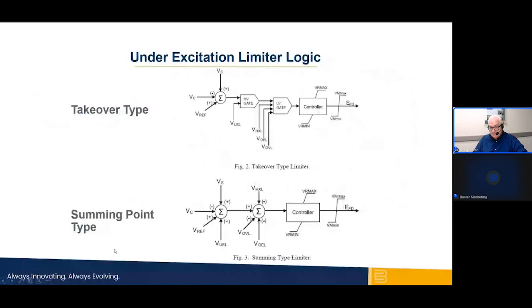Digital excitation controllers include the UEL as integrated in the same hardware as the AVR. The variety of formats includes the takeover type and the summing type. For the takeover type of the UEL, the pickup of the UEL condition is seen as an output to auctioneering inputs, either the AVR or the UEL in control, that puts the AVR or the UEL in control of the field output of the exciter. The summing point acts as a compensator for the AVR's error detector.